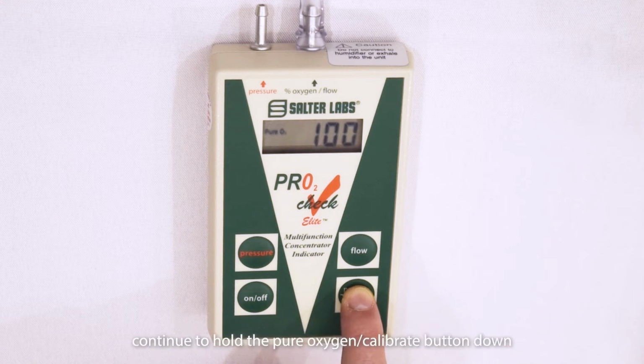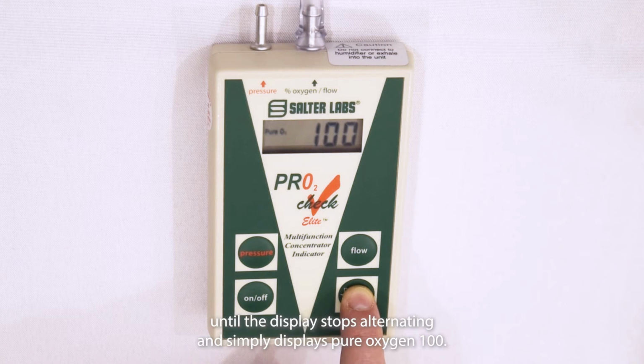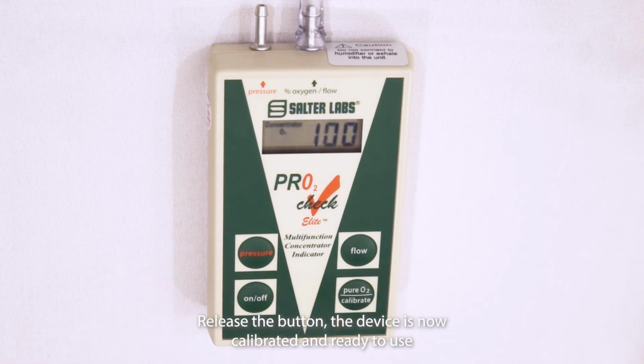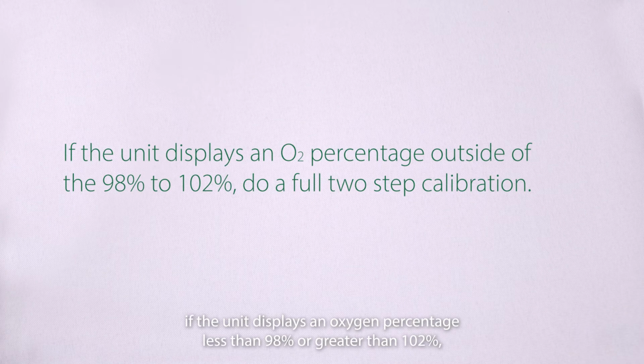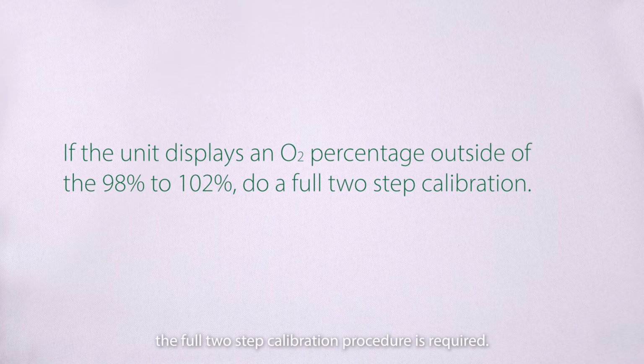Continue to hold the Pure Oxygen Calibrate button down until the display stops alternating and simply displays Pure Oxygen 100. Release the button. The device is now calibrated and ready to use.